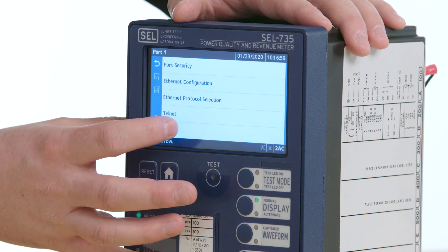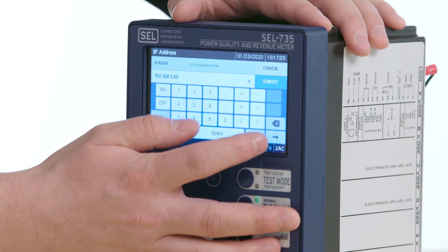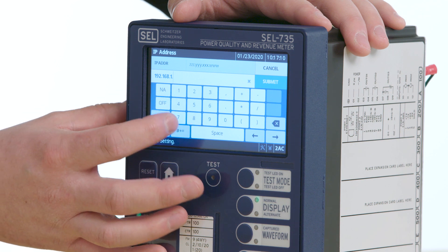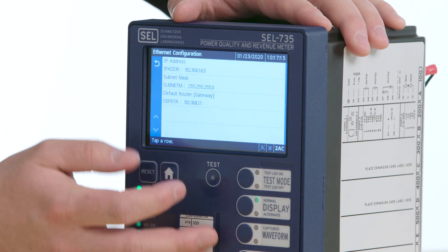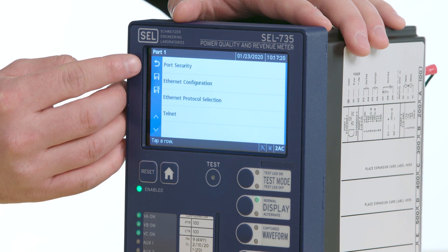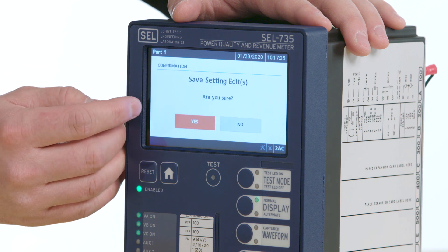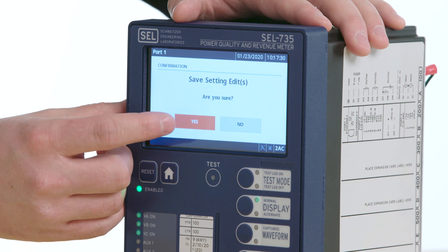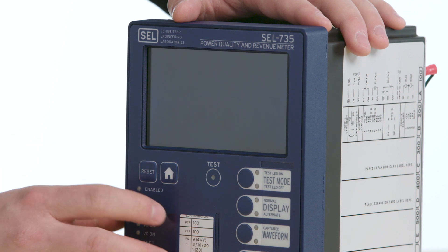Here I will change the IP address of the meter. The IP address we will use is 192.168.1.63 and click Submit. From here, press the back button, which will then give you the save and not-save icons. By clicking the save icon, I will be prompted to either save or discard the settings changes. I will select yes and save the new IP address.